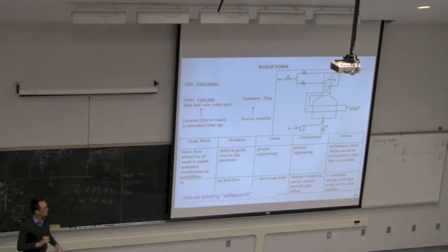Okay, so if we were in this class trying to do the full P&ID for the system, we would then go and add on a fuel valve. Yeah, so we'd add, like we did a few classes ago, that three-way solenoid valve. We'd go add one of those onto our drawing. So close fuel valve, great. Anything else? Would you probably also want to relieve pressure if there is any in the existing pipes in the furnace? So relieve pressure in the pipes.